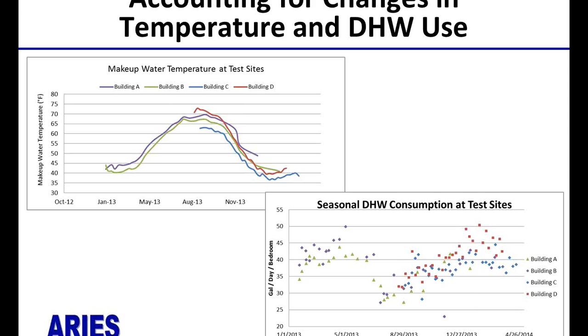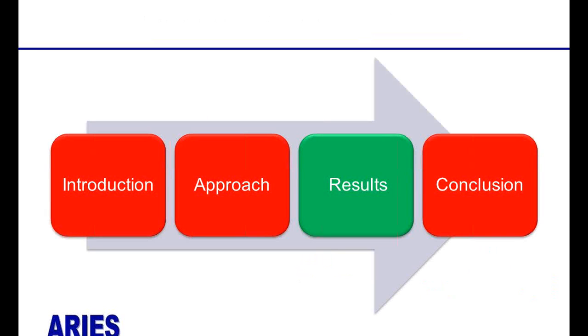These 2 graphs illustrate the point of varying consumption over the winter and summer seasons. So you can see in the top left, the makeup water temperature coming from our surface water reservoirs in upstate New York varies by quite a bit, about 30 degrees Fahrenheit from summer to winter. And also in the bottom right graph, you can see that gallons per day per bedroom roughly increased by 30–40% from summer to winter, and that's behavioral.